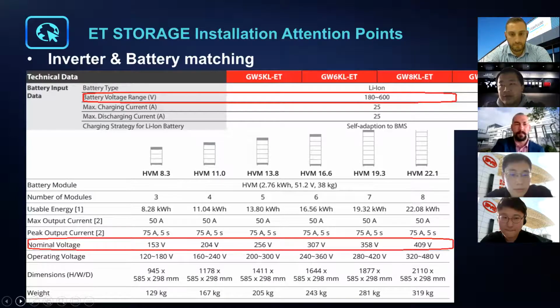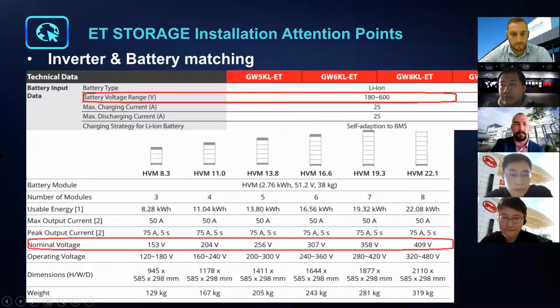For high voltage hybrid inverters, every inverter has a battery voltage range. When you design the system, you need to make sure your battery voltage stays in this range. For example, the BYD HVM 8.3 kWh battery, which has only 3 battery stacks, has a nominal voltage of only 153 volts. Compared with our battery range of 180 to 600 volts, this voltage is too low for the inverter to operate. So you basically cannot use this HVM 8.3 kWh together with our three-phase ET series.